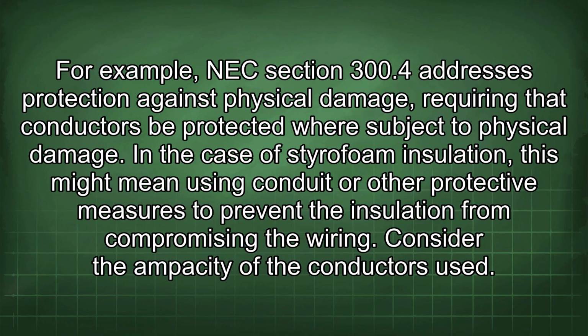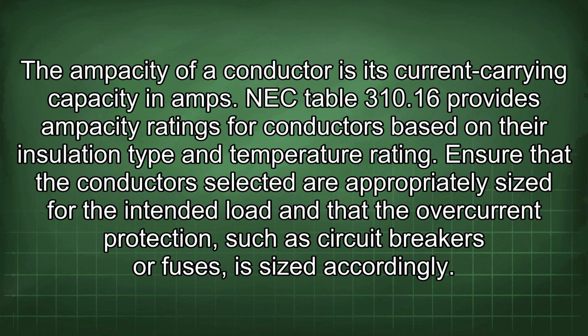In the case of styrofoam insulation, this might mean using conduit or other protective measures to prevent the insulation from compromising the wiring. Consider the ampacity of the conductors used. The ampacity of a conductor is its current carrying capacity in amps. NEC Table 310.16 provides ampacity ratings for conductors based on their insulation type and temperature rating. Ensure that the conductors selected are appropriately sized for the intended load and that the overcurrent protection, such as circuit breakers or fuses, is sized accordingly.